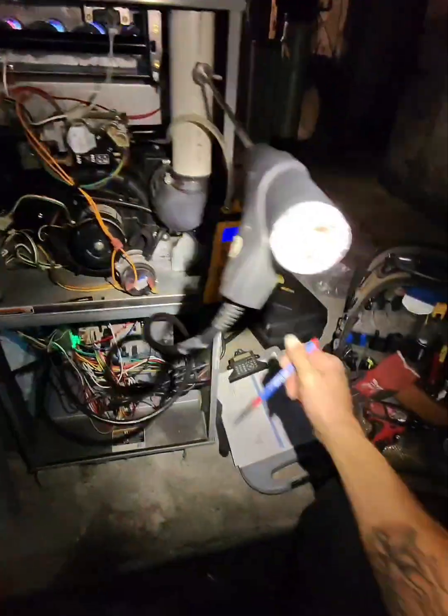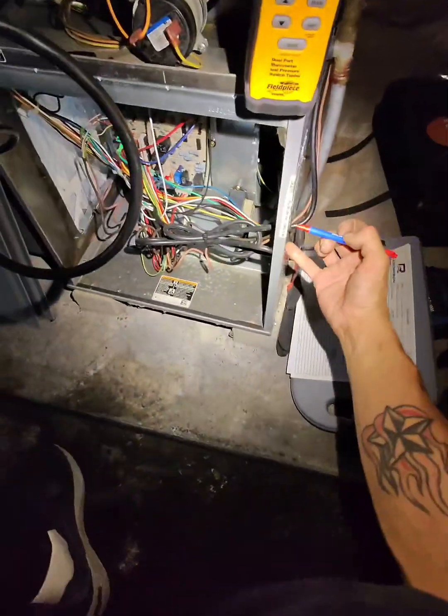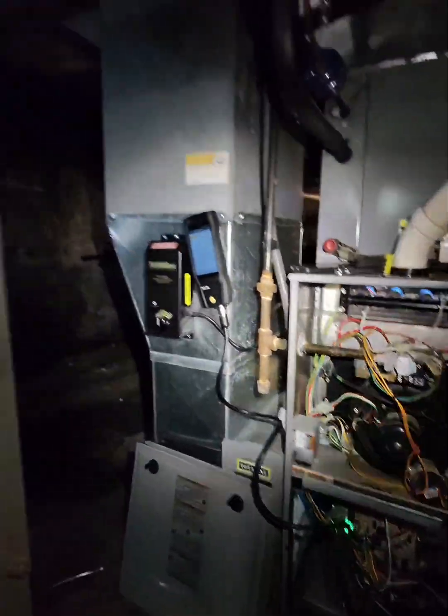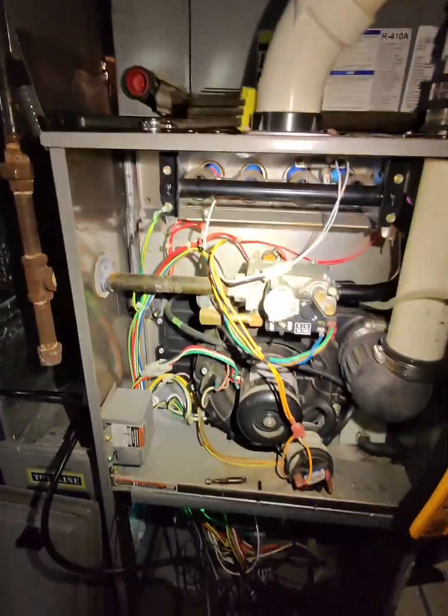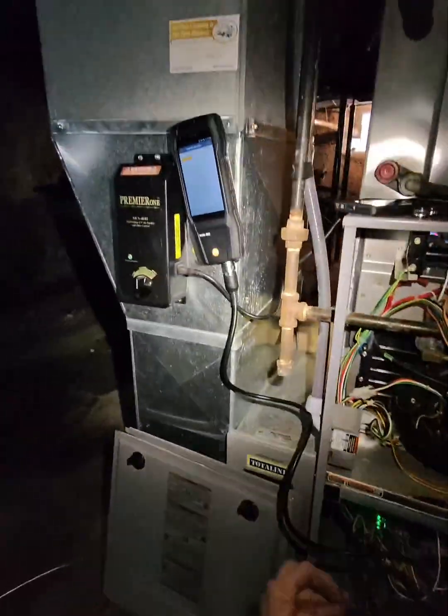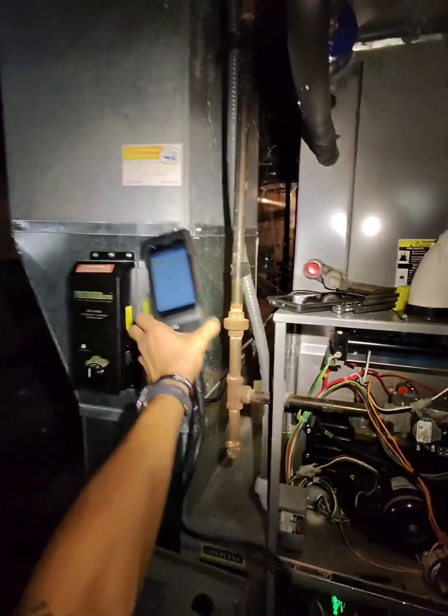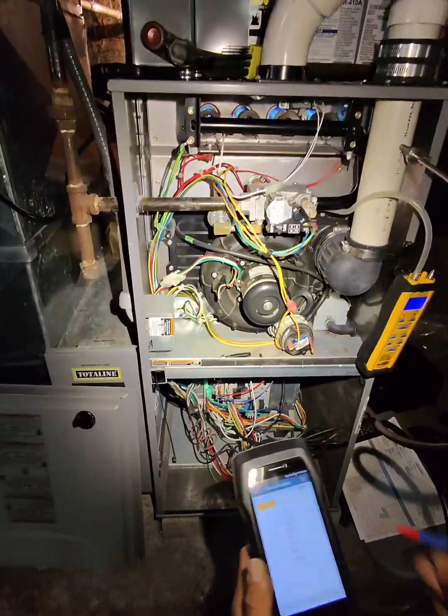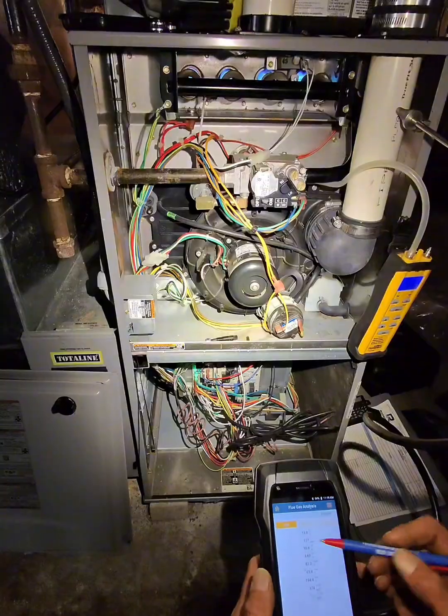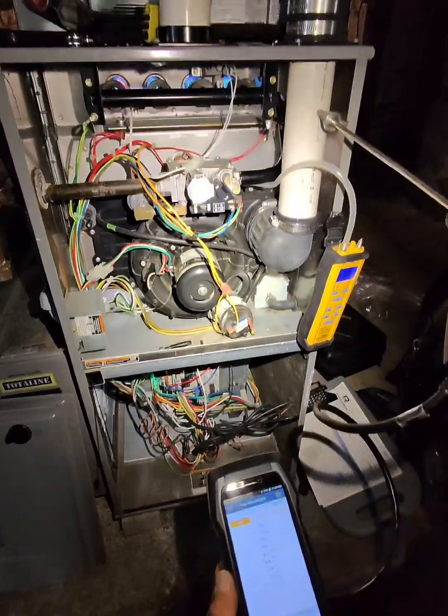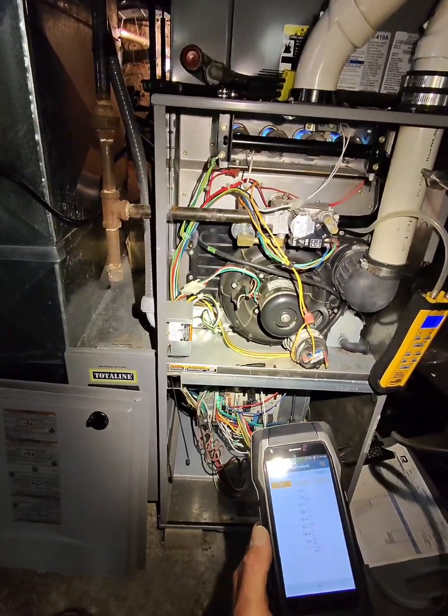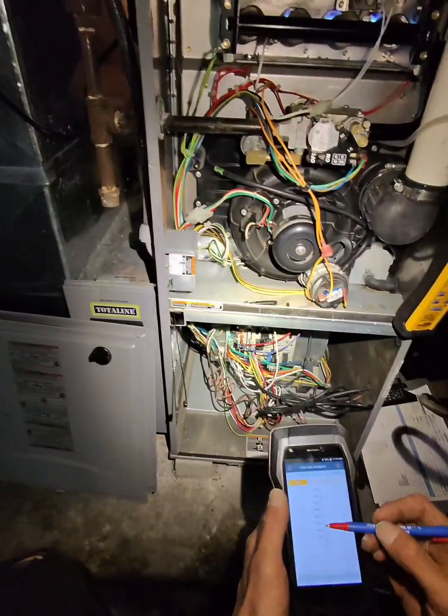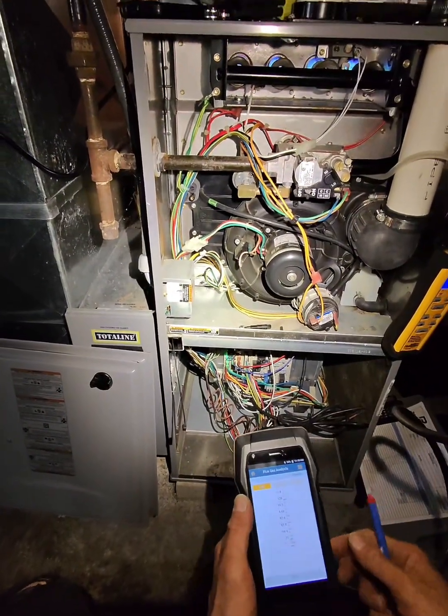So I'm doing a clean and check here on a Tempstar Carrier furnace from 2011. This is a propane furnace, and what I'm finding here is when we do the combustion analysis, the CO parts per million is up at 127 parts per million in first stage at 5.68 inches of water column, the gas pressure. Another thing that I want to note is the excess air right here at 194 and 194.